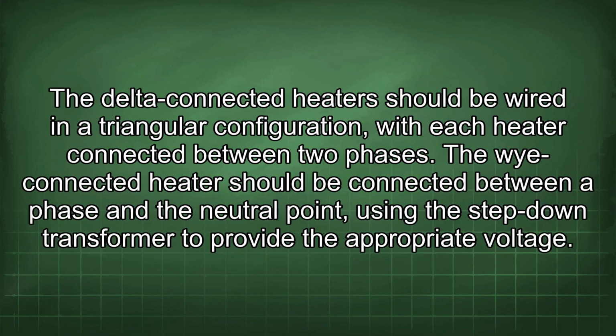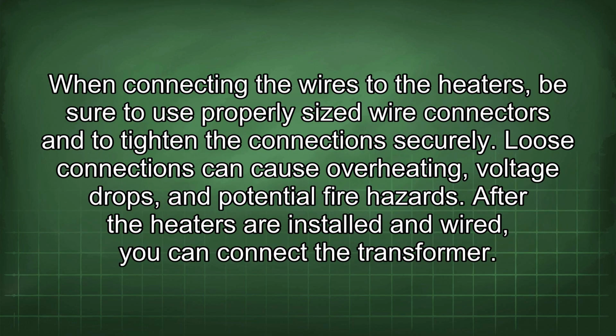The Delta-connected heaters should be wired in a triangular configuration, with each heater connected between two phases. The Y-connected heater should be connected between a phase and the neutral point, using the step-down transformer to provide the appropriate voltage. When connecting the wires to the heaters, be sure to use properly sized wire connectors and to tighten the connections securely. Loose connections can cause overheating, voltage drops, and potential fire hazards.